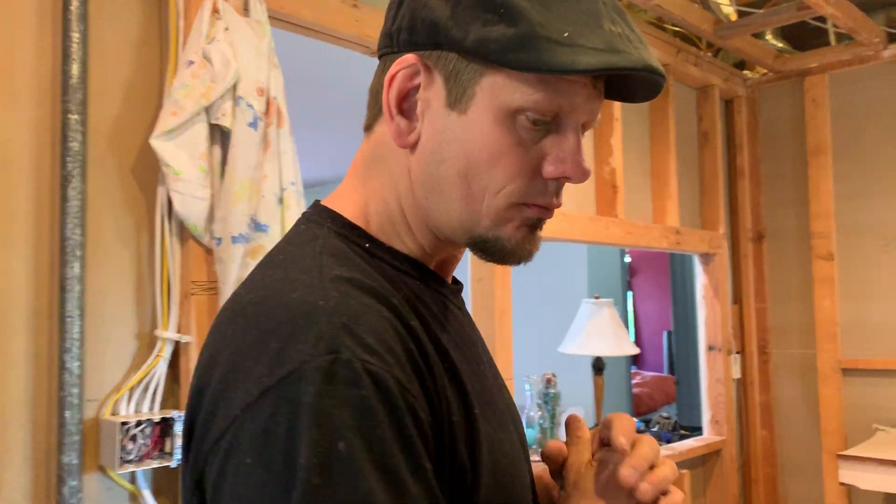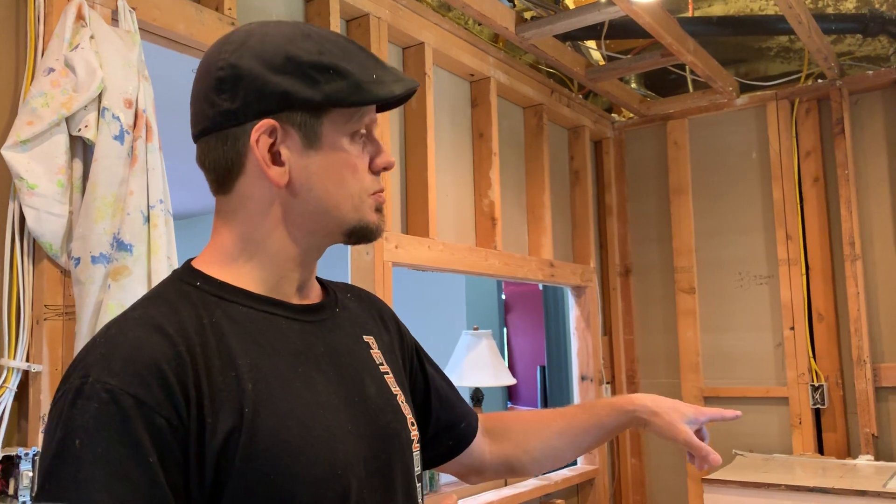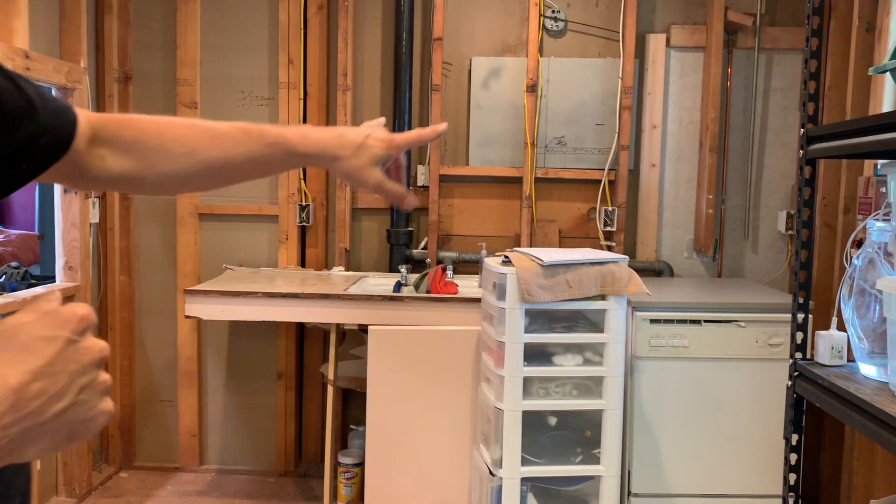That's exactly why we dual-function the garage. The panel was able to accept that breaker. A lot of times in Colorado, realtors call asking whether to GFCI just two outlets in the kitchen — that's a negotiating term. But that has nothing to do with redoing the kitchen from scratch with new wires. When you're redoing a kitchen, you have to GFCI-protect pretty much every 120-volt circuit in there.